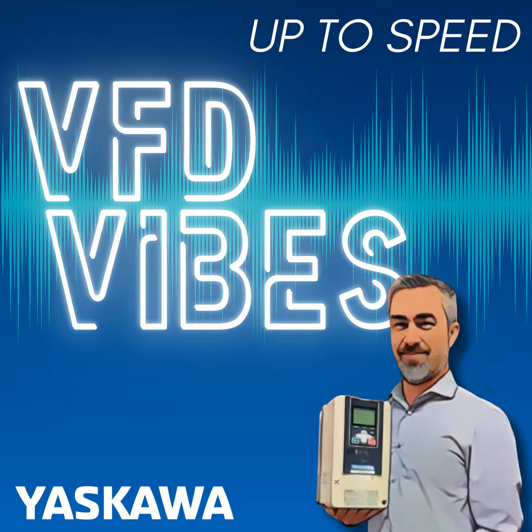So to wrap things up, installing a VFD is just the beginning. To get the most out of it, focus on proper installation, especially by trained personnel, motor and cable matching, auto tuning to get that accurate model of the motor and the best accurate and efficient performance you can. Drive features like energy savings modes and sleep functions. And remember to keep your preventative maintenance up to date and on schedule, and to keep that heat under control. Do all of that and your drive will not only save energy, it'll serve you reliably for years to come.